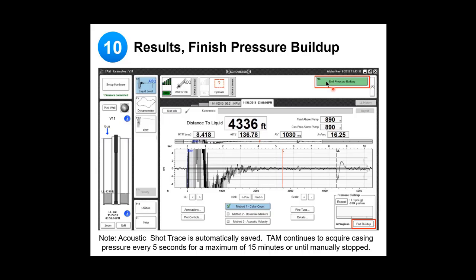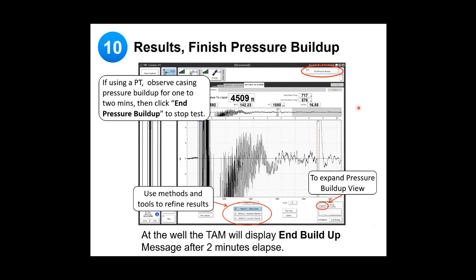Now, whenever you do the pressure buildup, we always request that you have at least a 2-minute buildup of good linear measurements. Those measurements in TAM are going to be taken every 5 seconds, allowing for a minimum of a 2-minute buildup. But if you need to let the buildup run longer, you sure can. We can actually have a maximum pressure buildup during a liquid level acquisition of up to 15 minutes. Once we are finished with the 2-minute buildup, it will prompt you with, do you want to end this pressure buildup? You can select yes or no, or you can manually end the buildup at any time that you want by clicking on end pressure buildup.